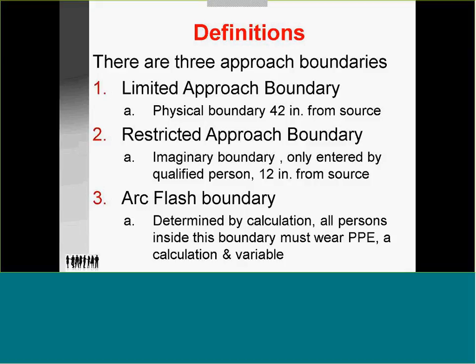All persons inside the boundary must wear PPE. Now, if the arc flash boundary is calculated at 60 inches, then the physical boundary of the limited approach must be extended out to the 60-inch mark. Inside that 60-inch mark you can sustain a severe or fatal burn. This is related to the discharge coming out of the panel. It is superheated air and material, and it rises rapidly.